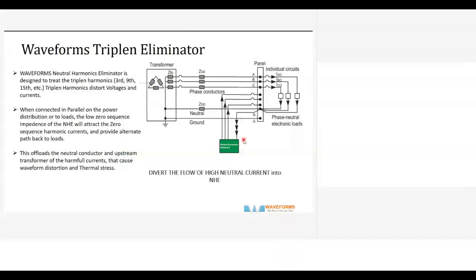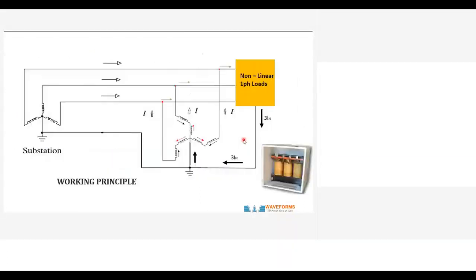So similarly, you have other SMPS, your computer, your music system, and so many other equipment that have only a single phase power supply. Besides that, you can have imbalance in your residential places. So in all this, you can improvise this design in such a way that you can install it along with the distribution transformer. To install this, you can offload this neutral current. You can prevent the failure of the bigger transformer.